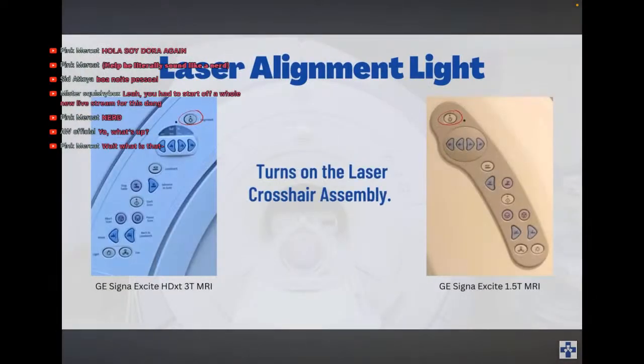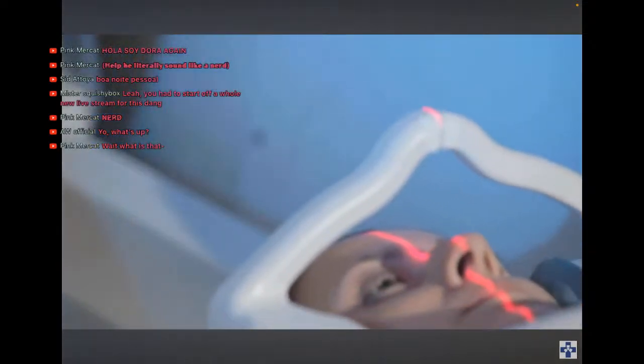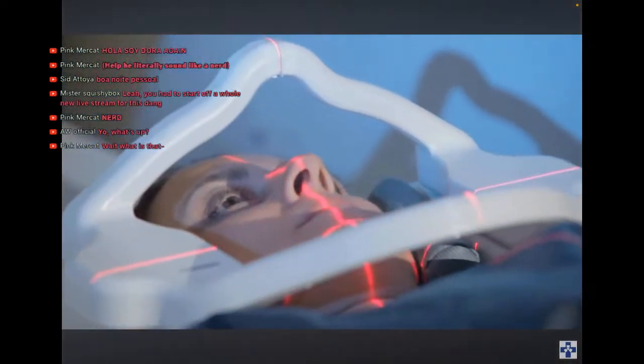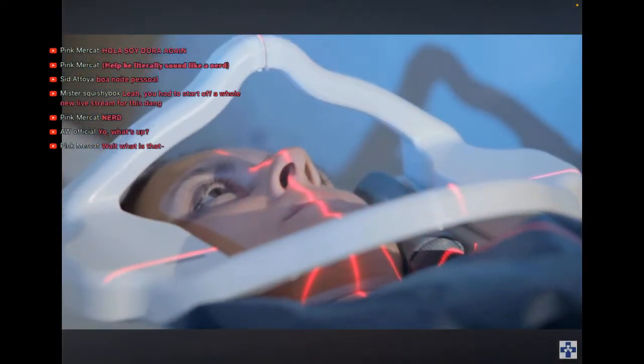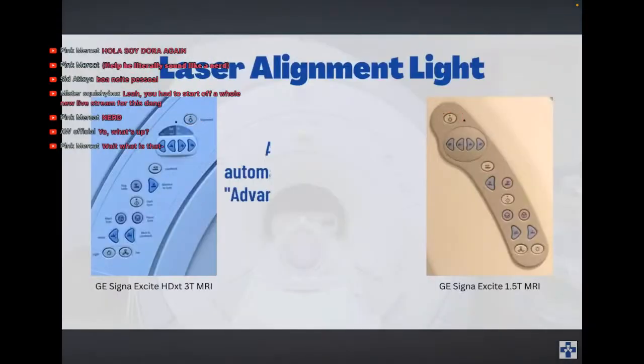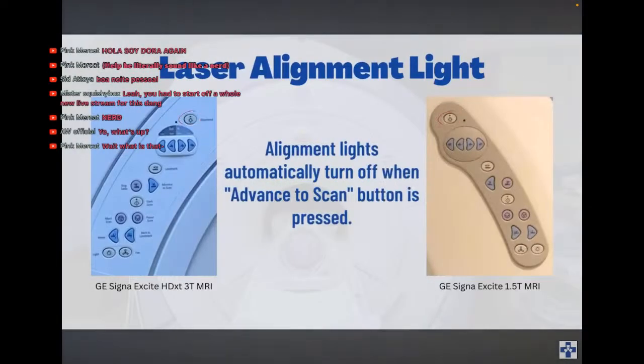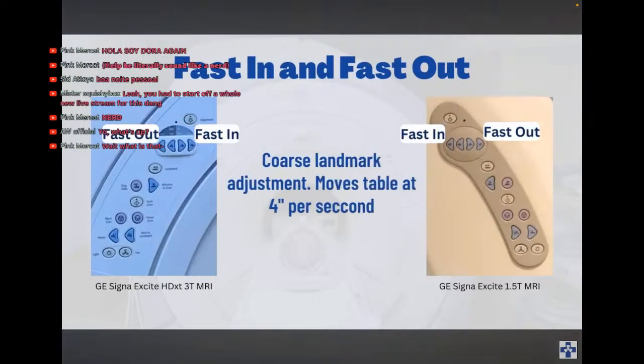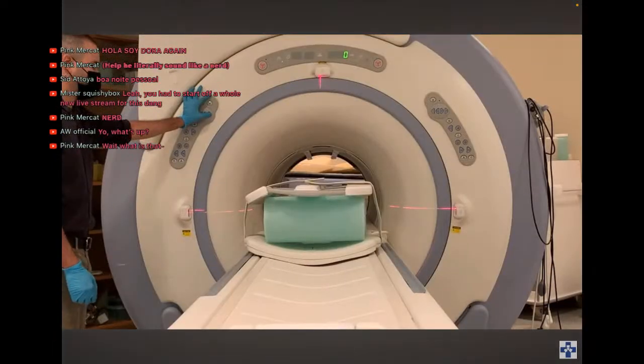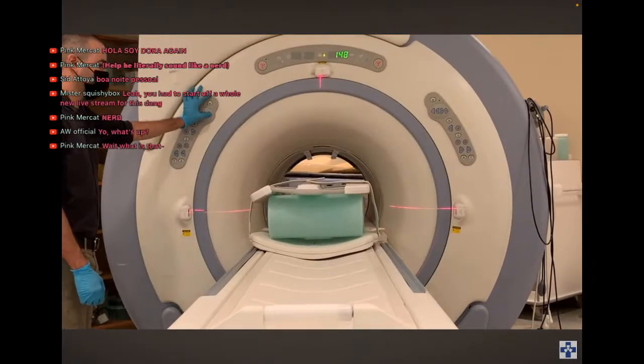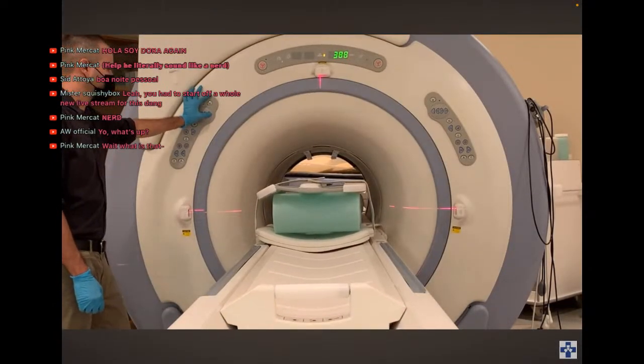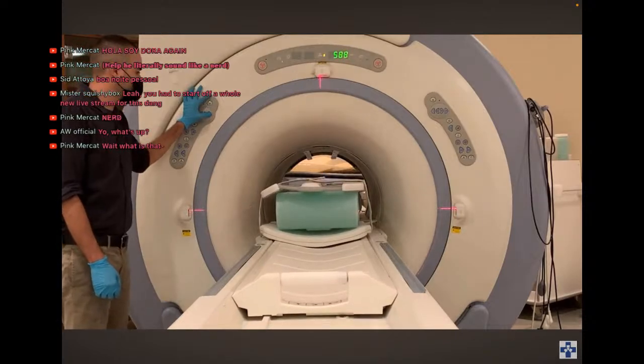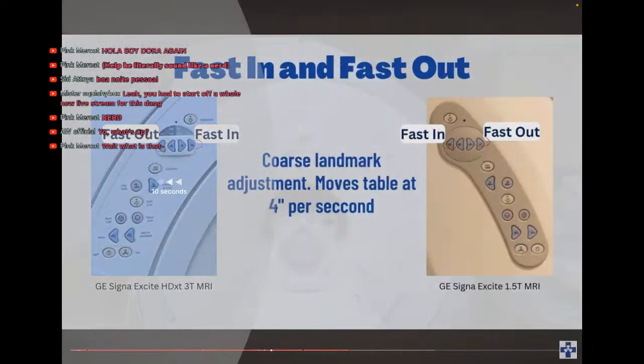The button at the top of the control panel powers the laser alignment light. This laser crosshair assembly allows for precision landmarking over the anatomical region of interest. Directly below the laser alignment button are the cradle directional controls. Fast in and fast out buttons move the patient into and out of the magnet at a rate of 4 inches per second.